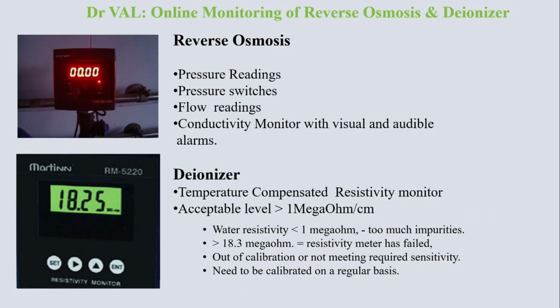If you are using a deionizer, because deionizers achieve a higher mineralogical purity, especially when they are used after the RO, conductivity means, as you can see, as the values go lower and lower, the least count of the instrument is decreasing. So something that reads like 0.00 may actually have a value that is somewhere like 0.05 or 0.06.